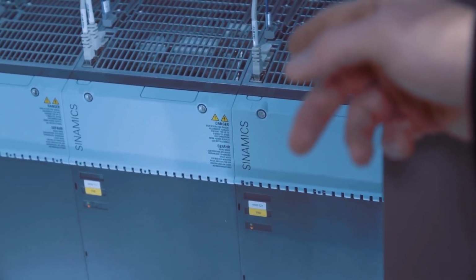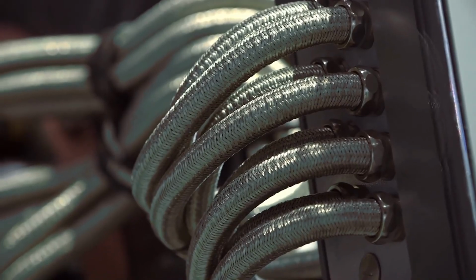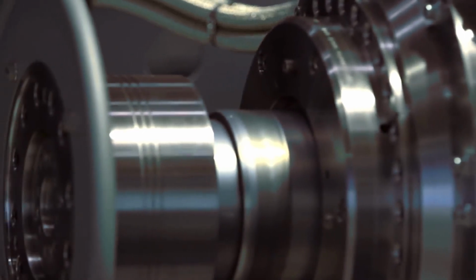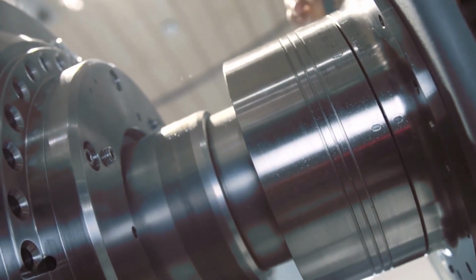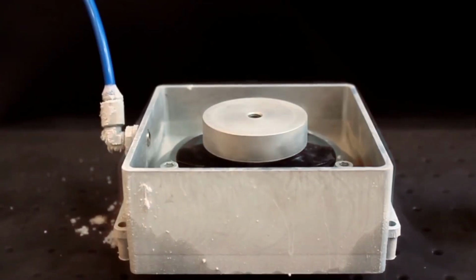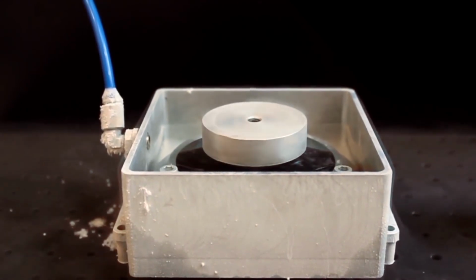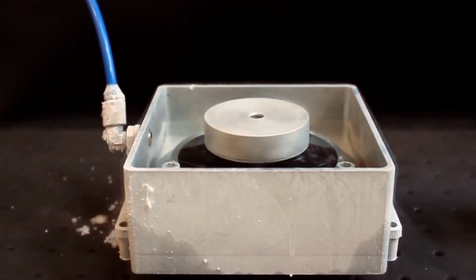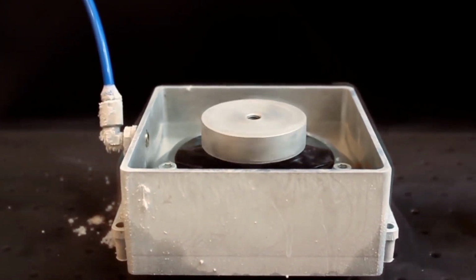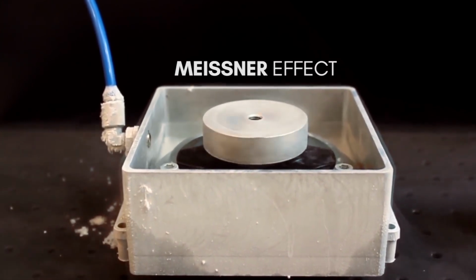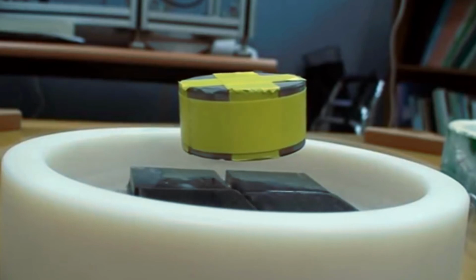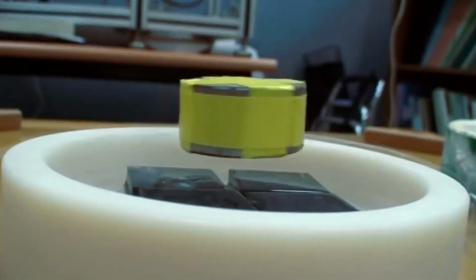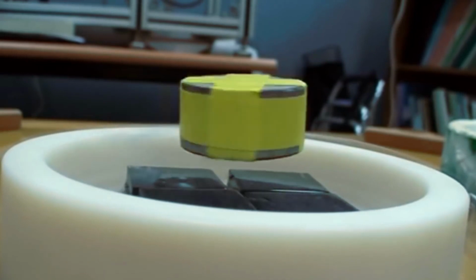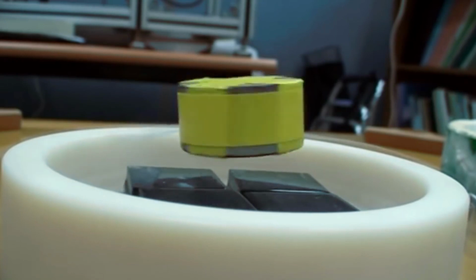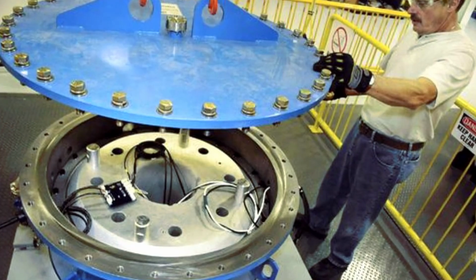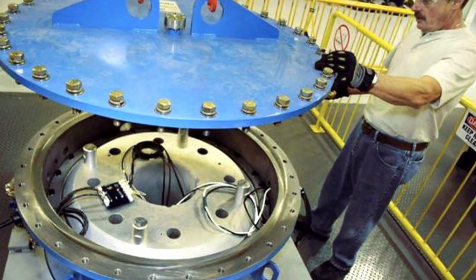Active magnetic bearings are high cost systems requiring complicated control mechanisms which consume energy to operate, adding to the overall losses of the bearing system. Magnetic bearing systems are capable of reducing parasitic losses down to about 1% of a flywheel's total storage capacity per hour. Superconducting magnetic bearings provide the best solution for high-speed flywheel energy storage systems, offering compact, frictionless, long-lasting, and stable operation. They stabilize the flywheel without electricity or positioning systems through the Meissner effect, expelling its own magnetic field and creating stable levitation. Superconductive magnetic bearings reduce losses down to well below 0.1% of a flywheel's total storage capacity per hour. However, this incredible efficiency comes at a high cost as they require a cryogenic cooling system in order to maintain superconductivity. Beyond the flywheel rotor, the housing of a flywheel storage system, though static, must be designed with containment in mind.